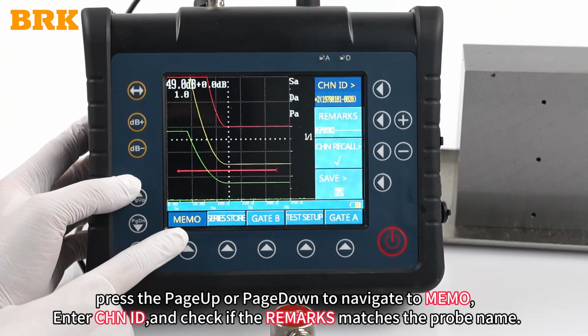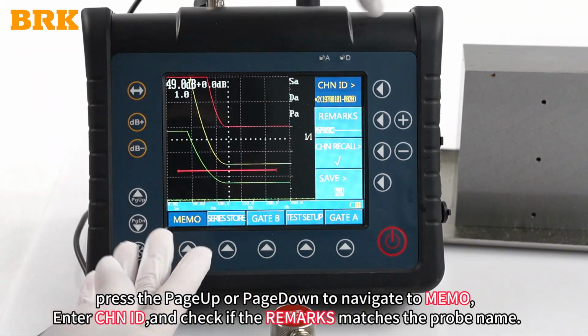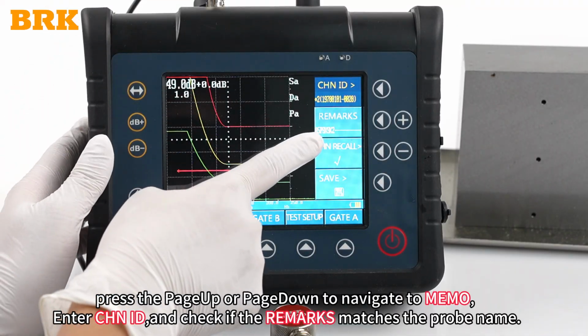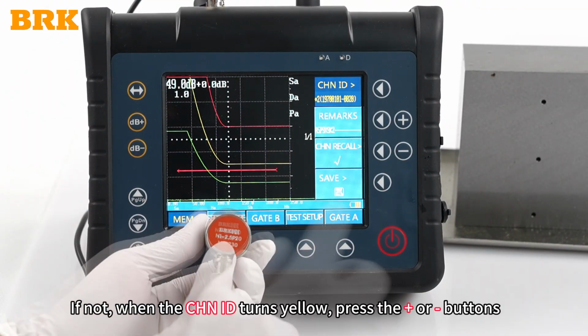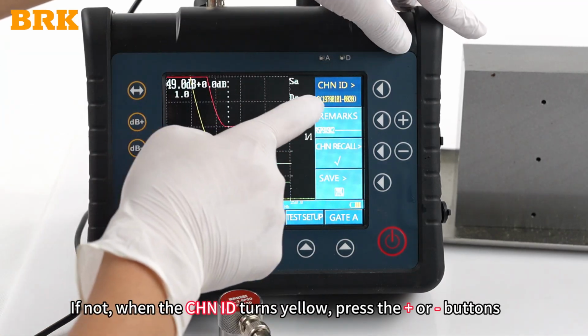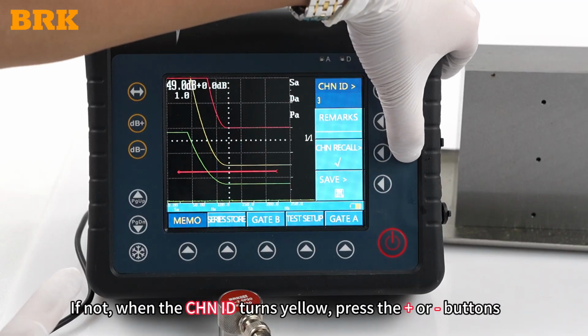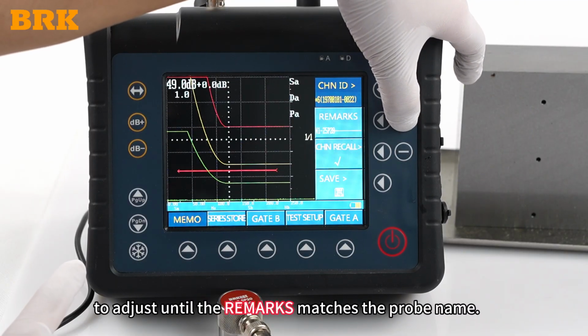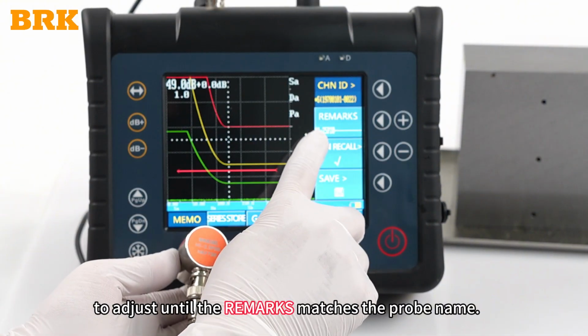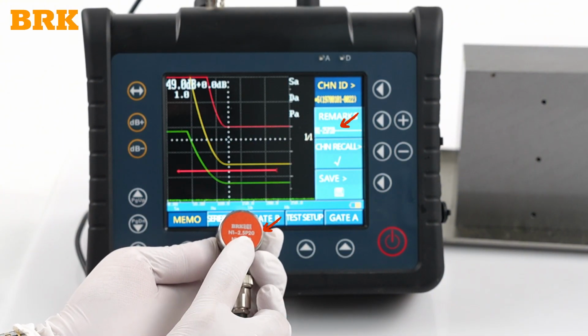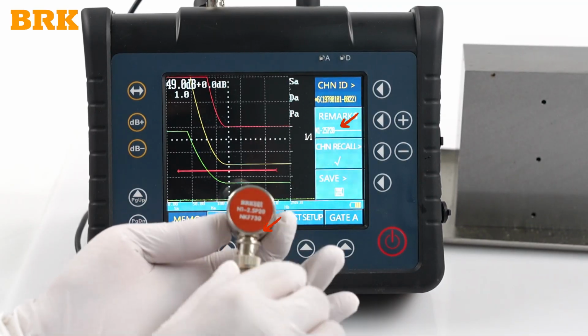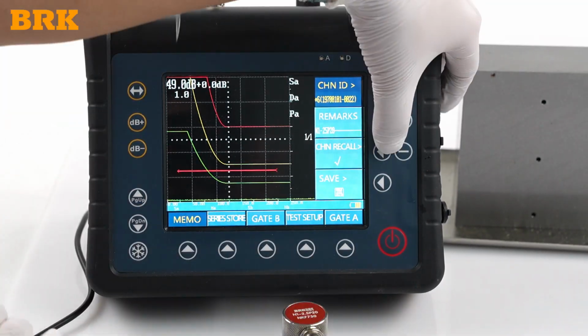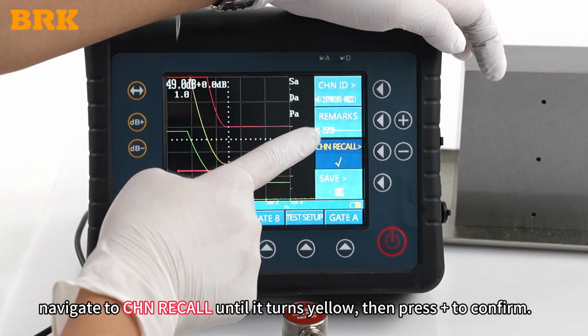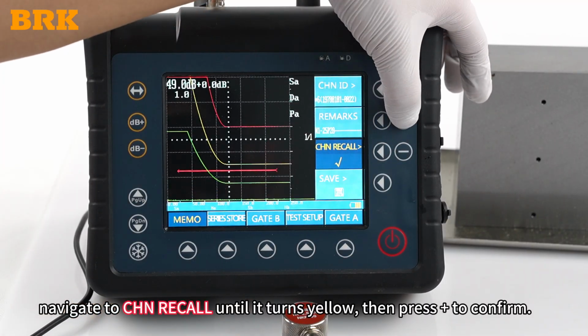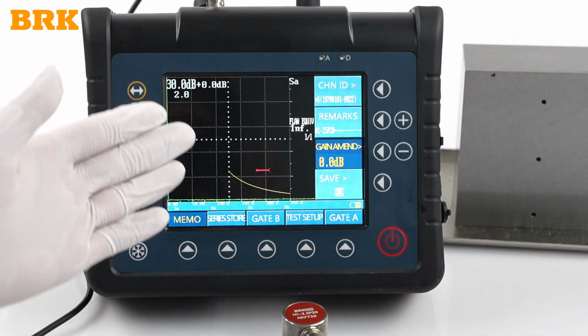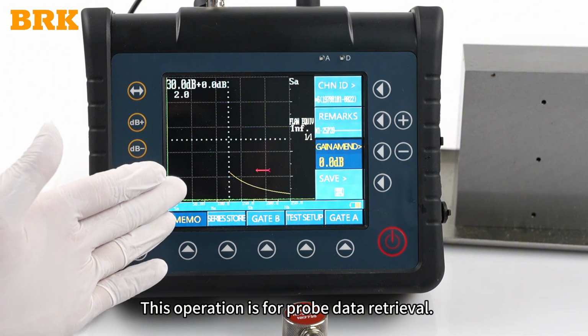Press the page up or page down to navigate to memo. Enter CHN ID and check if the remarks match the probe name. If not, when the CHN ID turns yellow, press the plus or minus buttons to adjust until the remarks match the probe name. After selecting the probe parameters, navigate to CHN recall until it turns yellow, then press plus to confirm. This operation is for probe data retrieval.